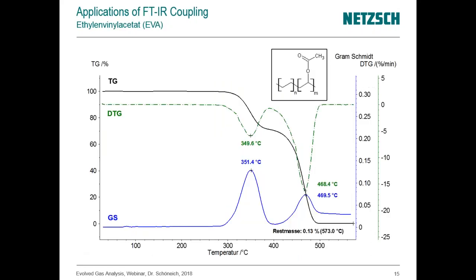From the application side, here is a common polymeric example: ethylene vinyl acetate, or EVA, used for instance in shoe soles. You can see the TG curve (mass change from the thermal balance), the DTG curve (derivative of mass change), and the Gram-Schmidt signal from the FTIR — which is essentially the integrated signal of the infrared spectrometer. For each mass loss step, you get a corresponding signal response from the FTIR, confirming that gases released during these decomposition steps are infrared active.